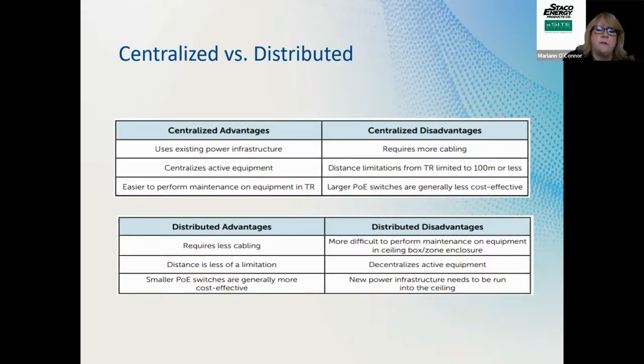So you also have distributed advantages. On the distributed, that's where the lighting inverter is accommodating that particular light fixture. So there is less cabling. Distance isn't as much of a problem, but the maintenance is more. So you're replacing battery packs, you're checking more points. So that takes more time. It costs more, and you also need to be conscious of some of the infrastructure needs in the ceiling for powering that. Next slide.